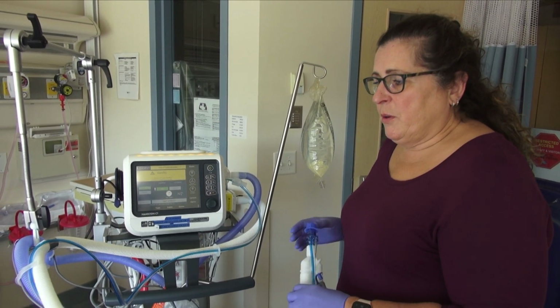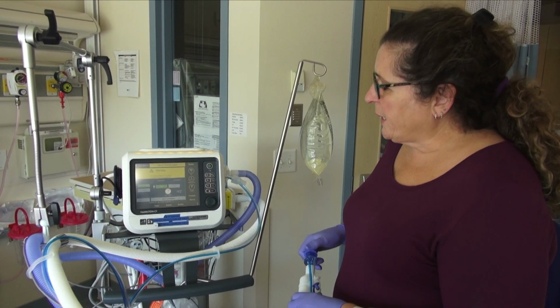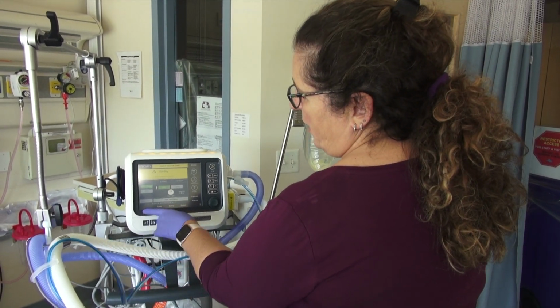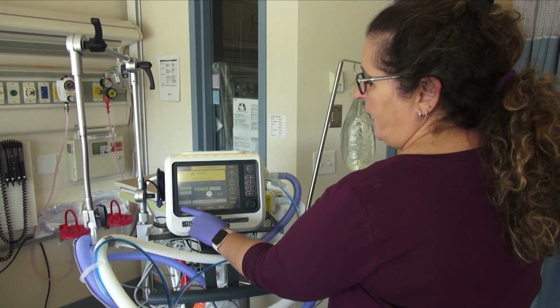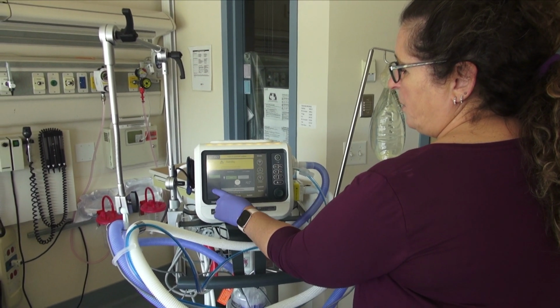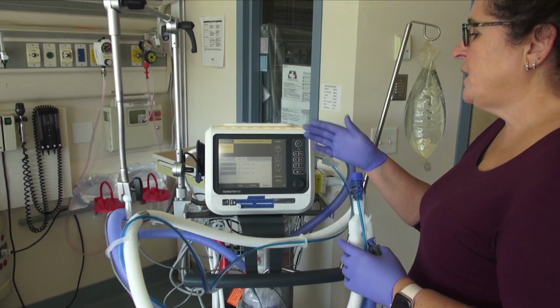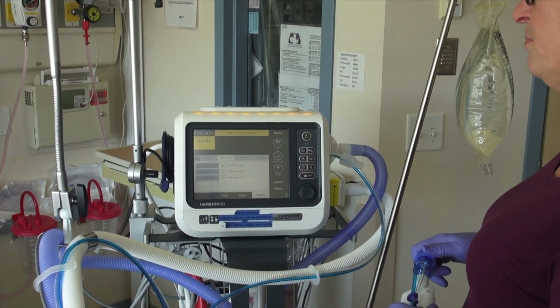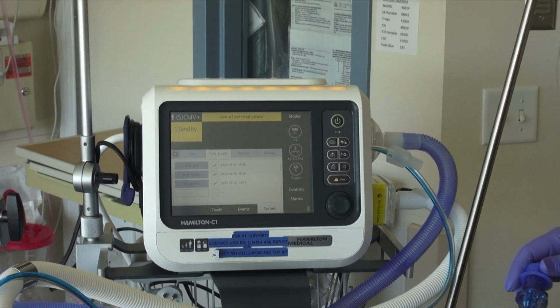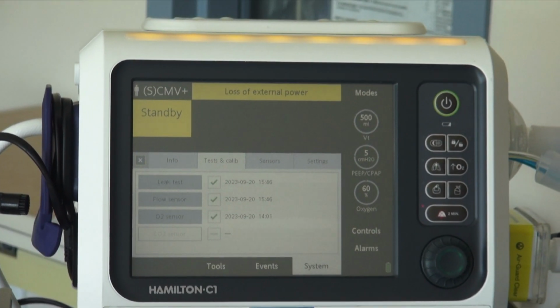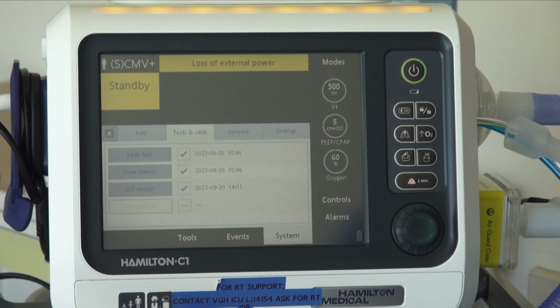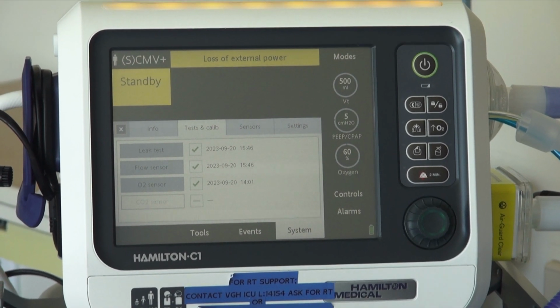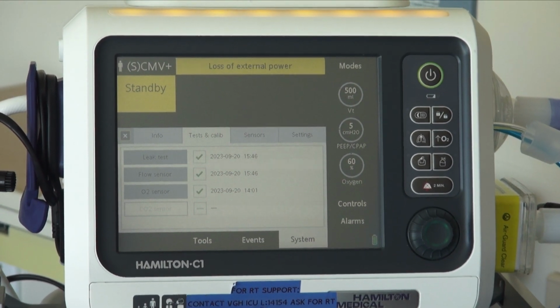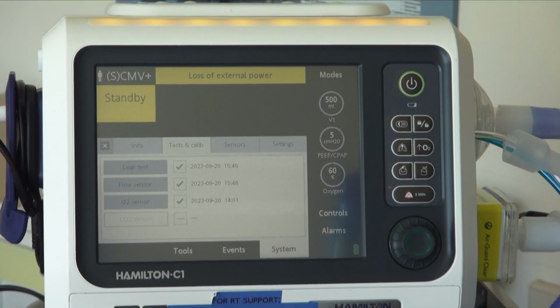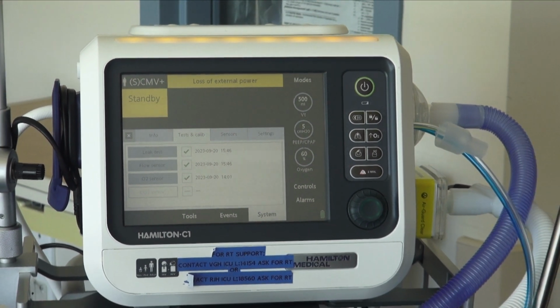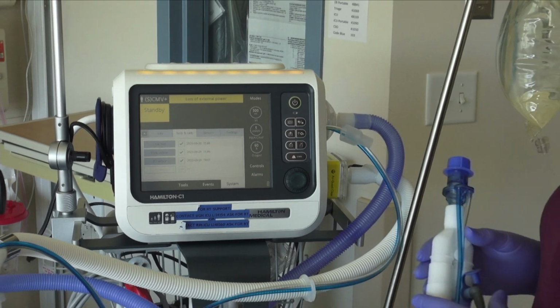Alright, so you've just set up your ventilator and you need to do a pre-op check. Your ventilator is on, your pre-op check is in the left-hand bottom corner. You're going to press on that and you're going to see 3 tests that can be done. We do the top 2, which is the leak test and the flow sensor test. The oxygen sensor test, we don't require to do it because the oxygen sensor test is constantly being checked while it's on the patient.